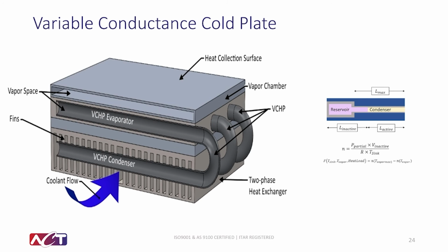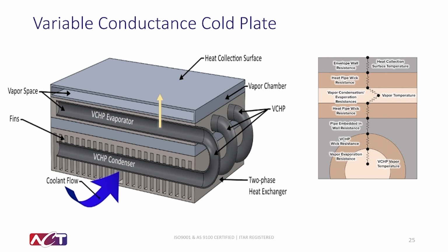So using these considerations, we are able to develop a function that is reliant on the vapor temperature, the sink temperature, and the heat load, which this function can then be formulated to determine the vapor temperature. With this more accurate vapor temperature, we could then use another thermal resistance network to model the heat transfer between the vapor of the heat pipe and the heat collection surface of the cold plate. With this completed model, we were able to vary different geometries of the system to find the optimal dimensions.